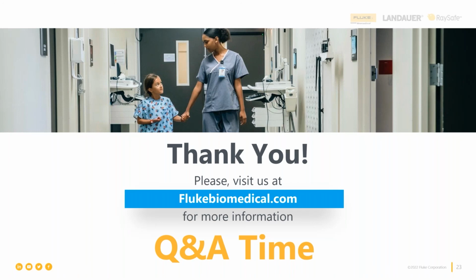The isolation is provided by line isolation transformers and line isolation monitors. We're not testing that line isolation system. The question is, how do I test a medical device that plugs in with a 3-prong plug or a 2-prong plug for electrical leakage inside an isolated power room? The advice of the standards committees is you shouldn't test to anything in that room, because all of what you think is a ground in that room is not connected to protective earth. It is connected to the secondary of the isolation transformer. Therefore you are missing some leakage current, and you need to know the worst case. You need to see all of the leakage current, which you cannot do inside the isolation.